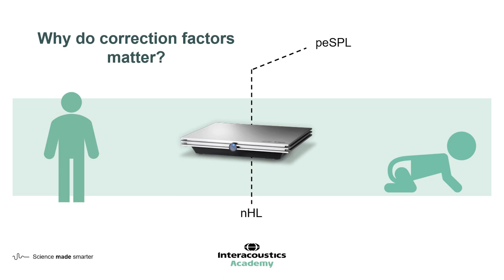Evoked potential systems should present stimuli levels in nHL. Historically there have been some unusual scales used, so it's important to check that nHL is the value presented by the system. We then apply a correction factor to get from nHL to EHL. This is as close to HL as we can get. We can't say that this is HL, because that is reserved for pure tone audiometry. Hence, in ABR we use EHL — estimated hearing level.